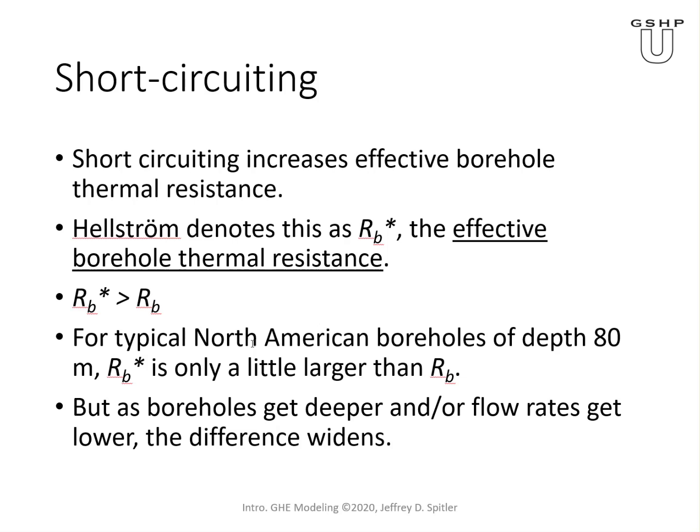When I first got into this about 25 years ago, I thought it wasn't a big deal. For a typical borehole of say 76 meters or 250 feet, RB star is only a little larger than RB — maybe off by one to three percent, not really worth worrying about. But boreholes have gotten deeper, and in places like Scandinavia the average borehole depth is around 186 meters. In that case, the effect of short-circuiting becomes larger and needs to be accounted for. It also becomes significant if you have very low flow rates.